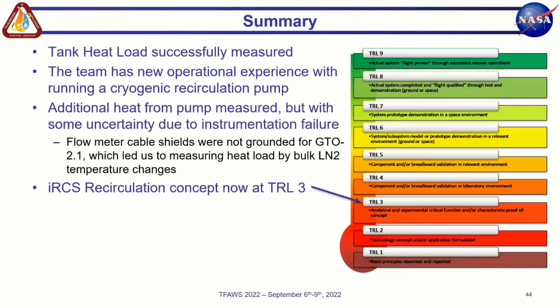In summary, we were able to successfully measure the tank heat load on CVT2. Our entire team was able to get some good operational experience with cryogenic recirculation pump. We were able to measure the additional heat from the pump, again, due to some instrumentation failure. We're not 100% certain on it, but we were able to get measurements, so that's good. We were able to increase our TRL level for the IRCS concept to TRL3.